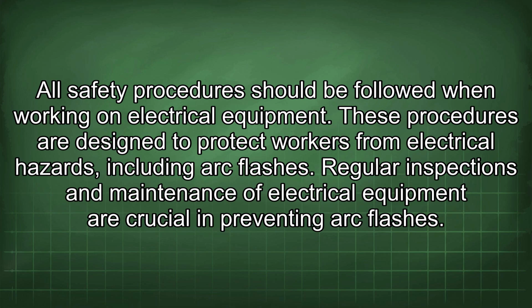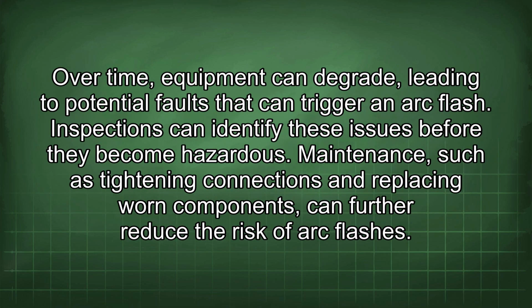Regular inspections and maintenance of electrical equipment are crucial in preventing arc flashes. Over time, equipment can degrade, leading to potential faults that can trigger an arc flash. Inspections can identify these issues before they become hazardous. Maintenance, such as tightening connections and replacing worn components, can further reduce the risk of arc flashes.